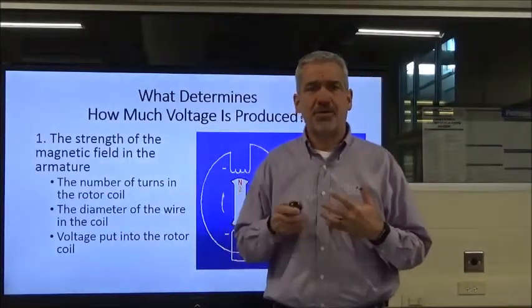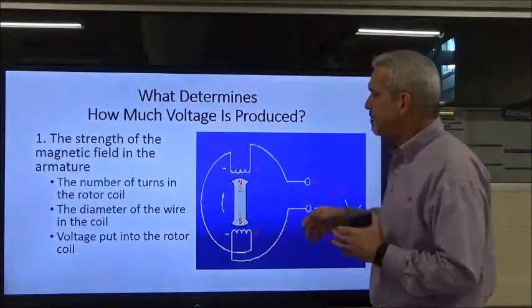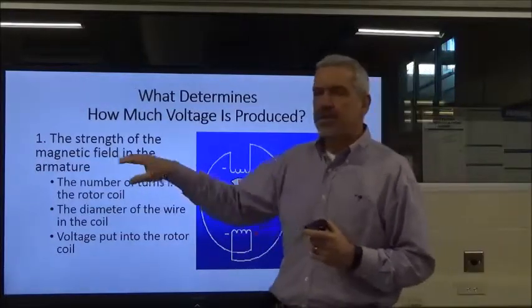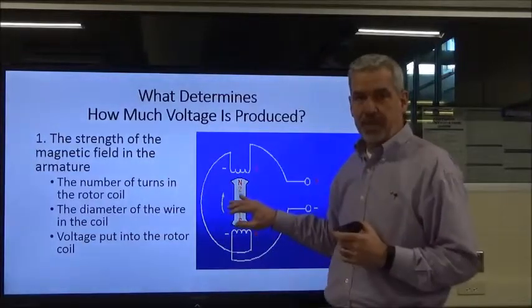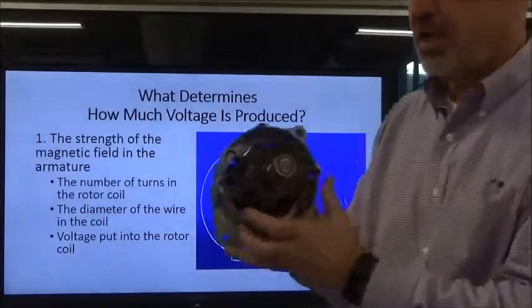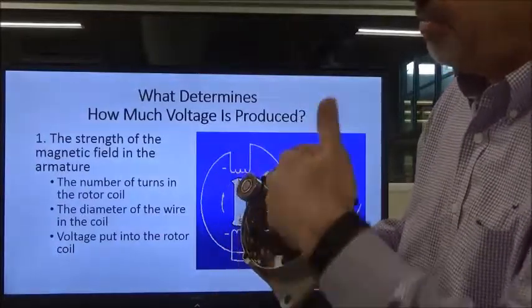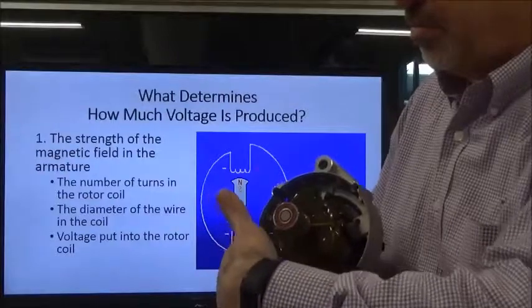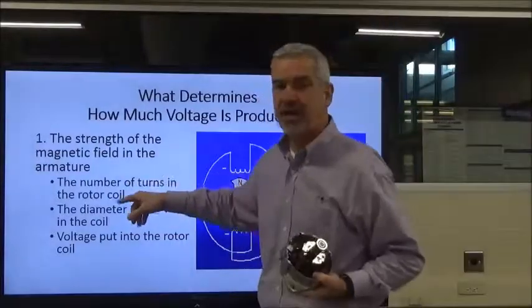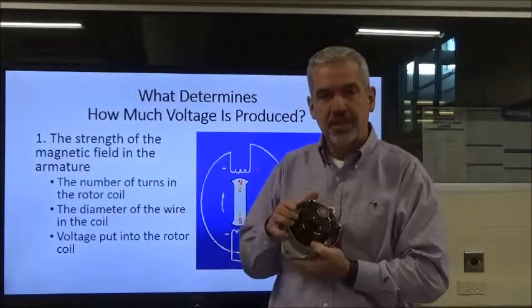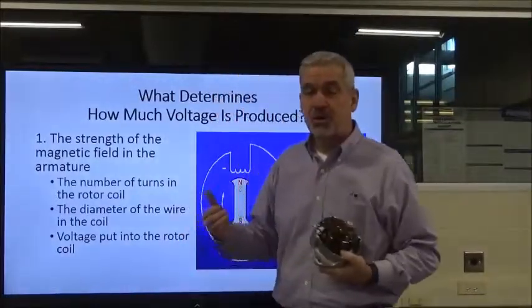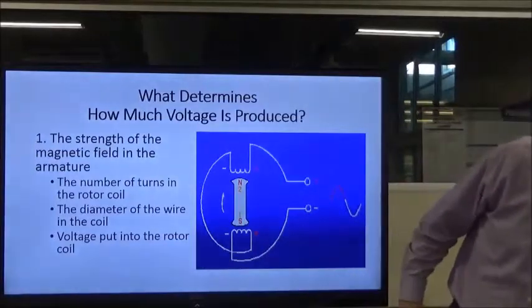A couple of things impact the amount of voltage that is created. Number one, remember we talked about turning our magnetic rotor through the coils of the stator. One of the things that affects the magnetic field in the armature of the rotor is the number of turns of wire in the coil. The number of turns — how many times we wrap that wire around the pole pieces — impacts how strong the magnetic field is. The more turns we have, the stronger the magnetic field. Also, the diameter of that wire matters: the thicker the wire, the greater the diameter, the stronger the magnetic field. And also the voltage actually being put into the coil impacts the strength of the magnetic field as well.